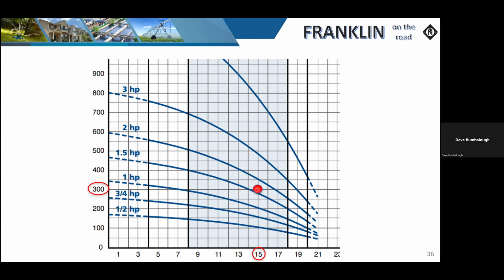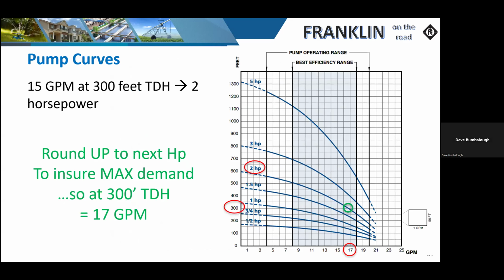So if I was to go back a couple of slides where we were looking at the pipe size going over to the house, I believe we had 1 inch in there. If we were to just upsize that, that would buy us a little forgiveness there and allow the TDH number to drop a little bit. I would probably get away with that 1.5 horse. Now granted, if we were to intersect that curve, we're only going to get about 14 gallons per minute. Could I live with that? I sure could. But if we absolutely needed 15 gallons per minute, we're going to have to step it up.